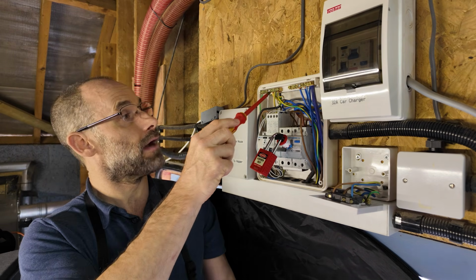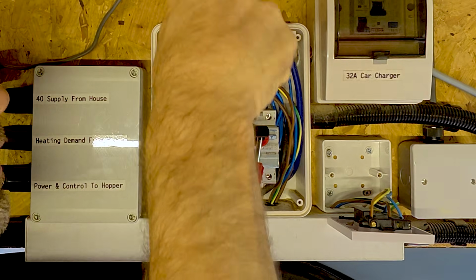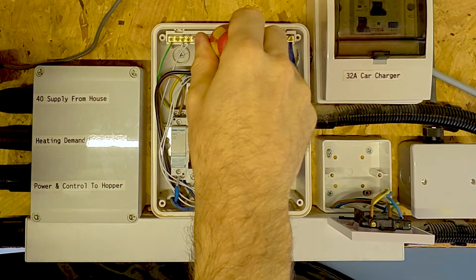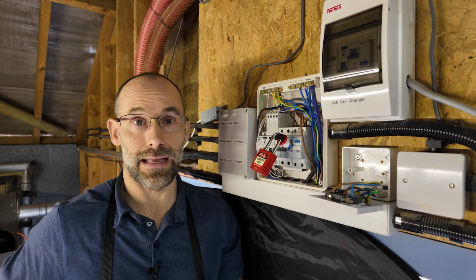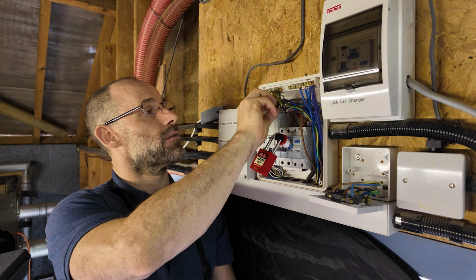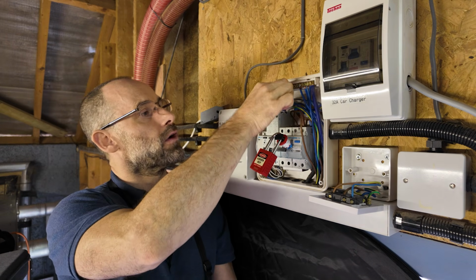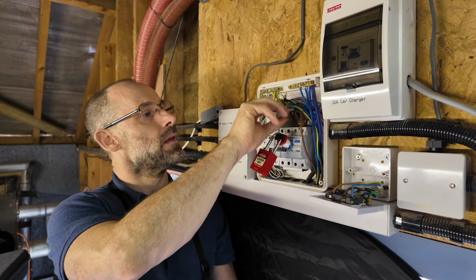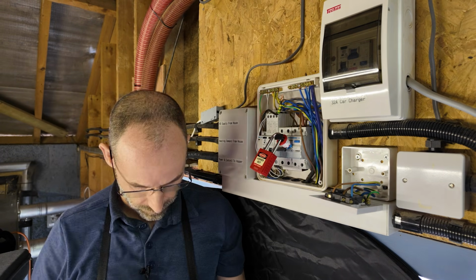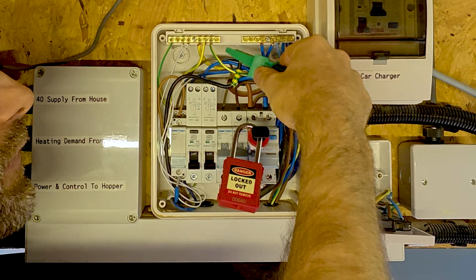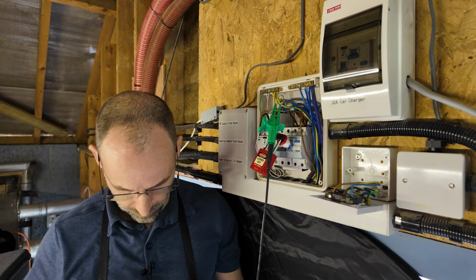We rarely do this, but we're going to disconnect our main earthing conductor because this entire board is isolated. So everything here is powered off, right? This is the only time we're going to disconnect this, and we're not going to disconnect it for any longer than we need to. So we disconnect that main earthing conductor like that. I get a probe lead on that. This is a 3-lead test, which is why we need the specialist equipment.